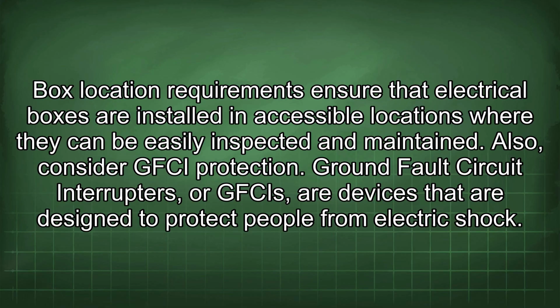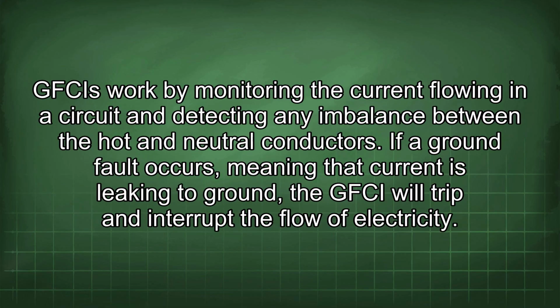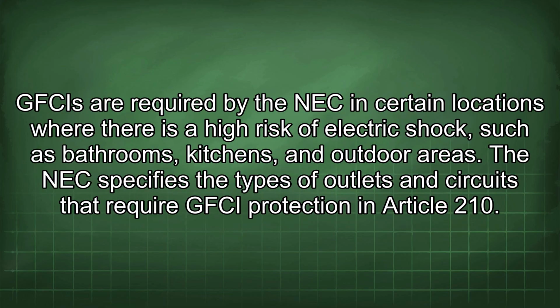Also, consider GFCI protection. Ground fault circuit interrupters, or GFCIs, are devices that are designed to protect people from electric shock. GFCIs work by monitoring the current flowing in a circuit and detecting any imbalance between the hot and neutral conductors. If a ground fault occurs, meaning that current is leaking to ground, the GFCI will trip and interrupt the flow of electricity. GFCIs are required by the NEC in certain locations where there is a high risk of electric shock, such as bathrooms, kitchens, and outdoor areas.